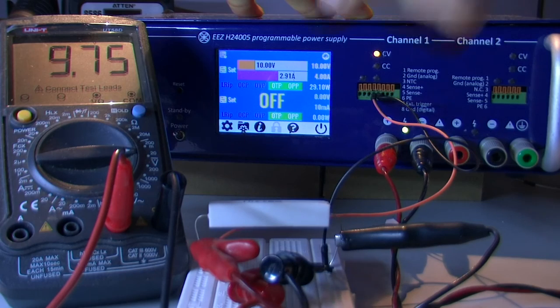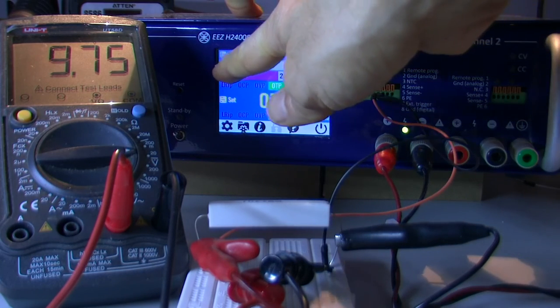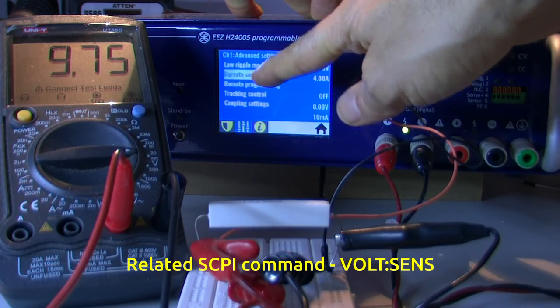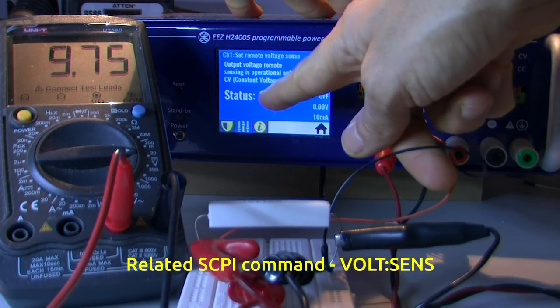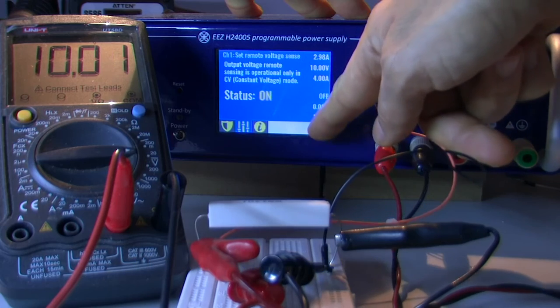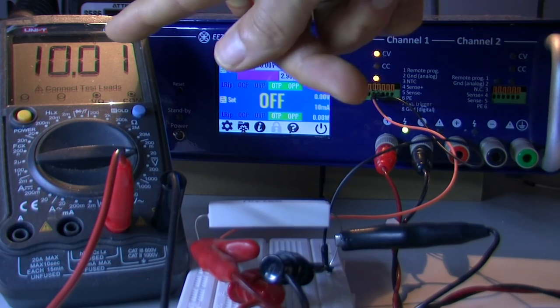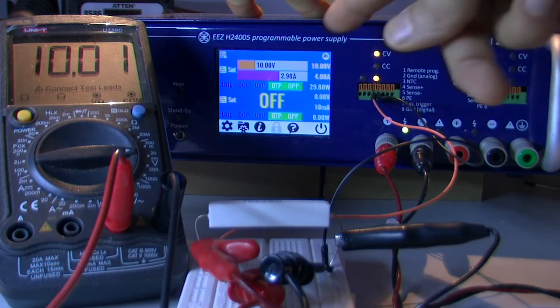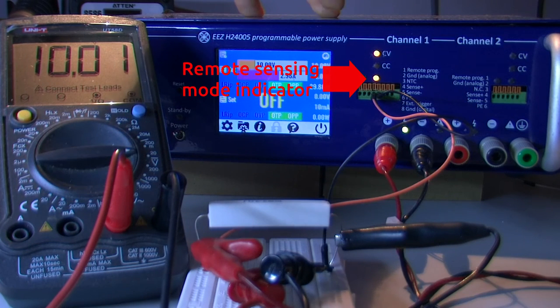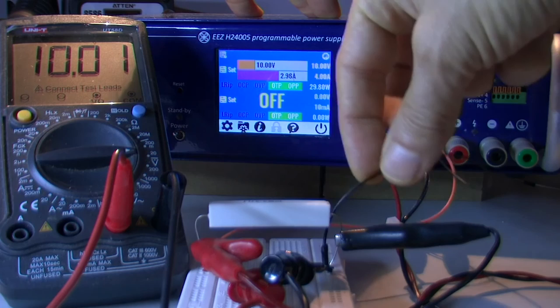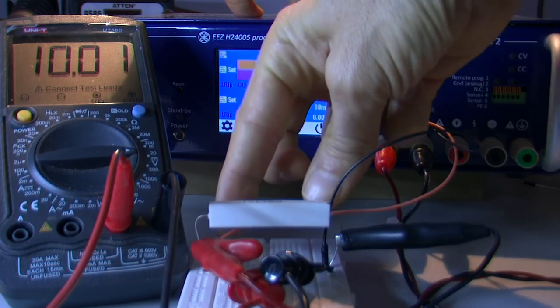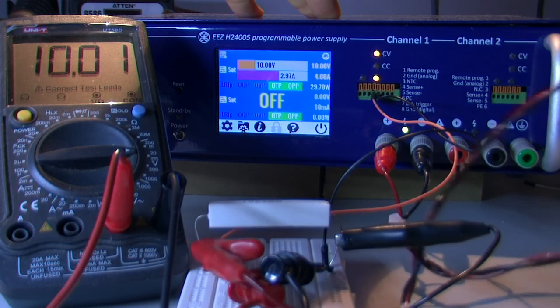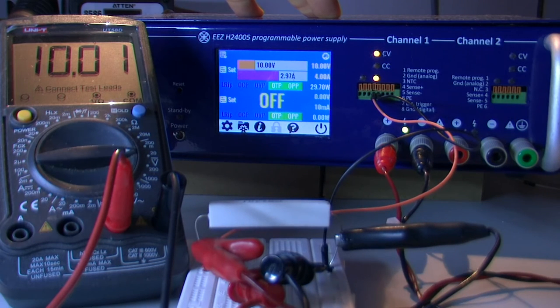We still cannot see any difference because remote sensing is not activated. Status is off. And now here we go. We have 10 volts like what is set because voltage is now measured directly on the load terminal, and all cable loss and connection loss is now compensated.